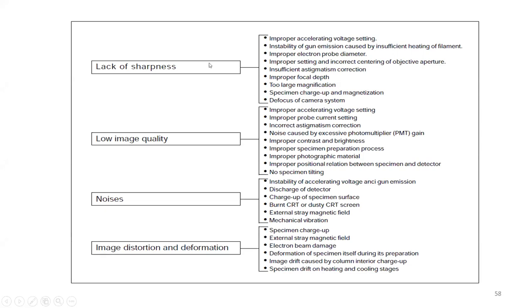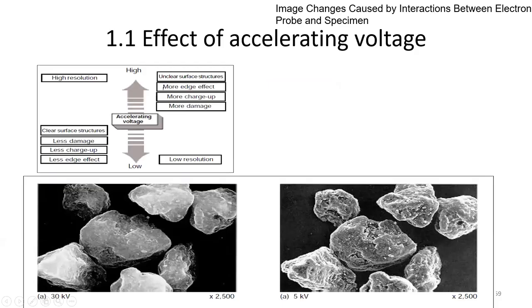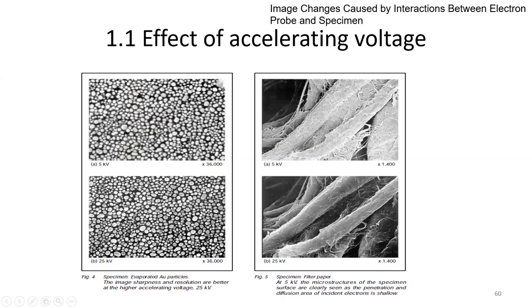There are several problems that one comes across, like lack of sharpness, low image quality, noise, image distortion and deformation. For example, here is the effect of accelerating voltage. At a lower kV on the right-hand side, 5 kV, you can see much more detail of your specimen, whereas at 30 kV, a higher kV, you cannot see the surface features. You can get high resolution at higher kVs, but with very unclear surface features, more edge effect, more problems. Again, here is the same thing: 5 kV gives you much more detail.